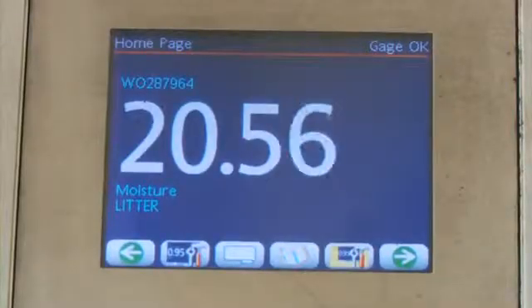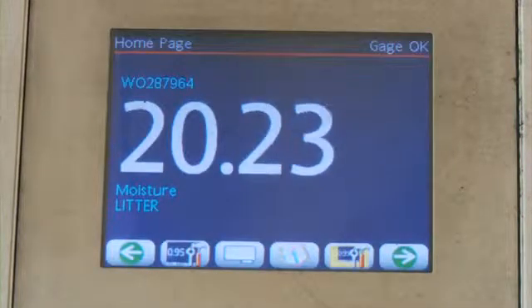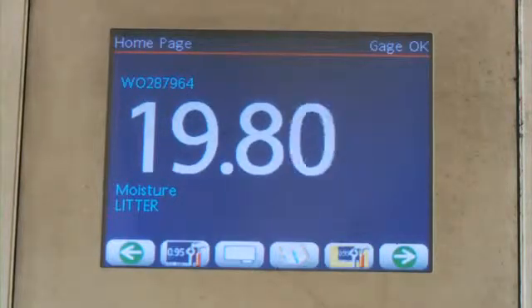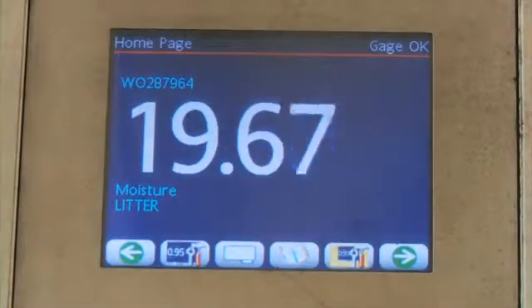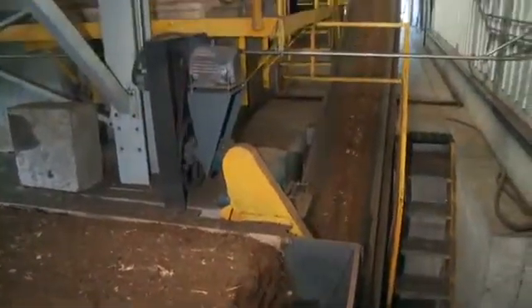The moisture content of the material is recorded to the digital system controls through this optical sensor. Most waste materials contain moisture, with some as high as 80%. If the waste fuel has a moisture content above 10 to 15%, a dryer should be considered in the system design. Next, the material is weighed on a weigh belt conveyor before entering the gasifier.